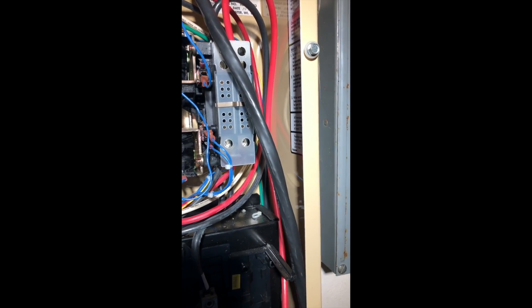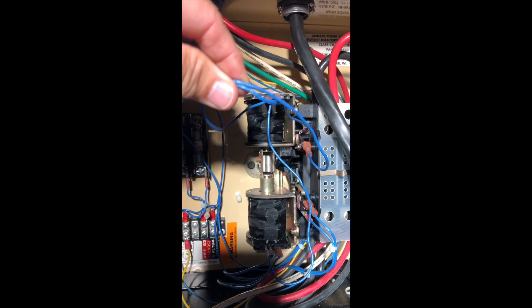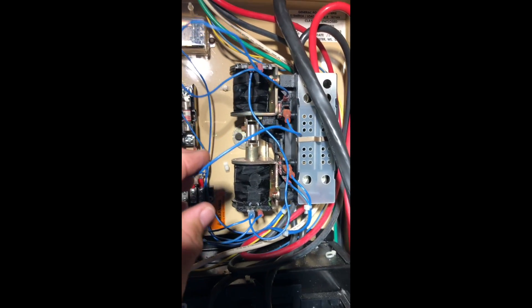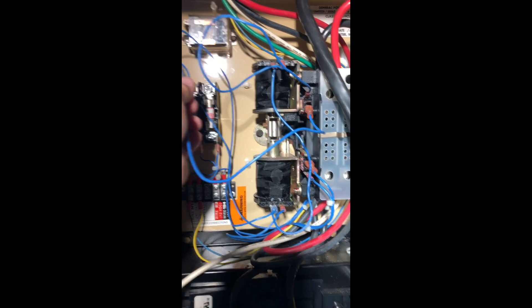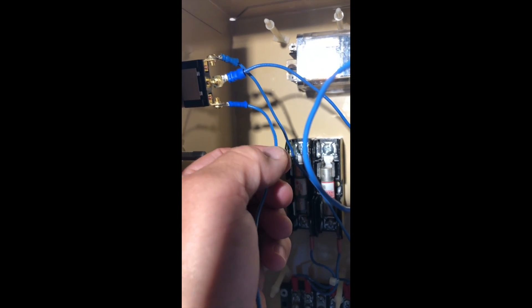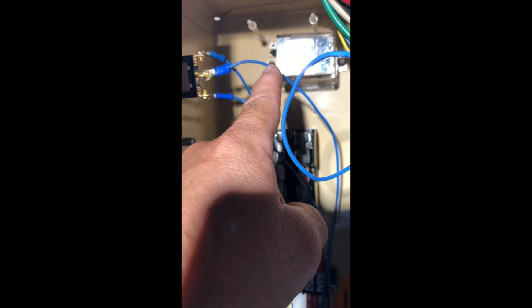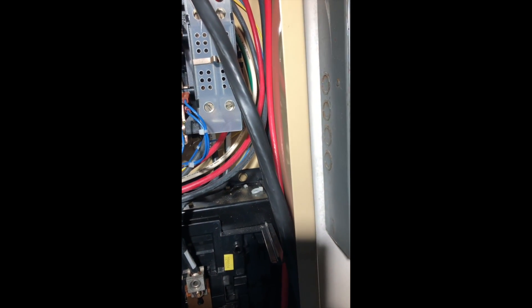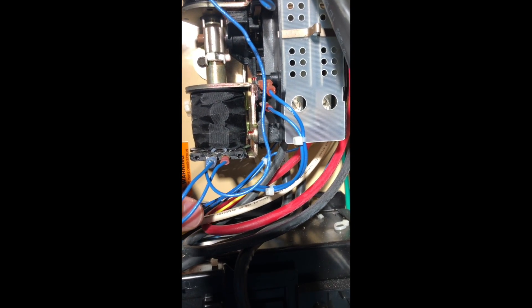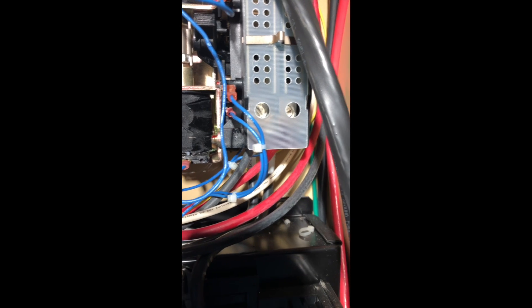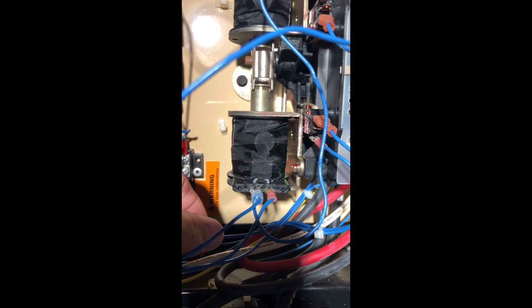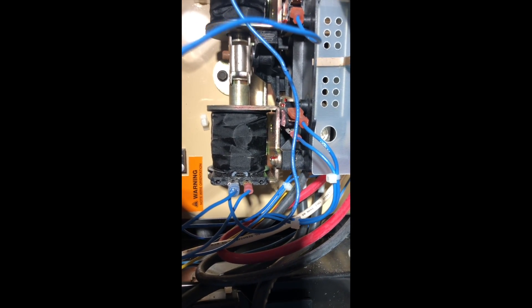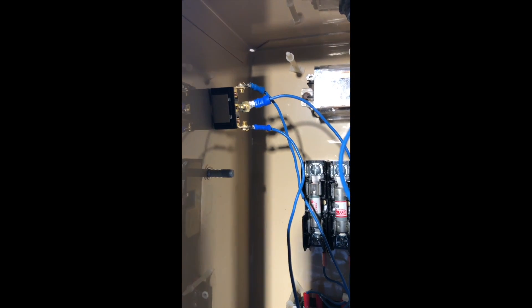So you have a top circuit, which is right here. Here's your top circuit, and then there's a center circuit which is the constant power. And you're going to get that from the lower lead right here. It's kind of hard to see, but this is existing, so you can find this in your panel. This is going to come off of one of the legs. I believe these are 240 electromagnets because to complete the circuit, it's both hot legs come together in your switch. Make sure you have a switch that's capable of 250 volts, which is what that one is.